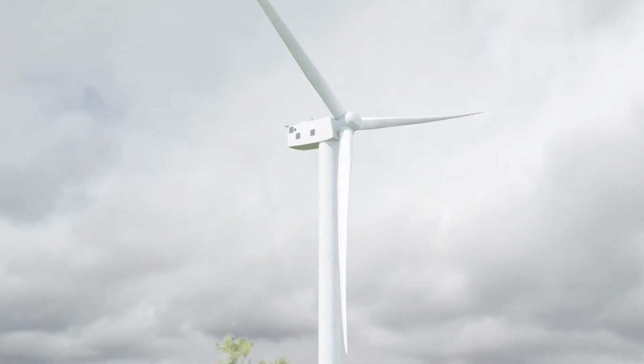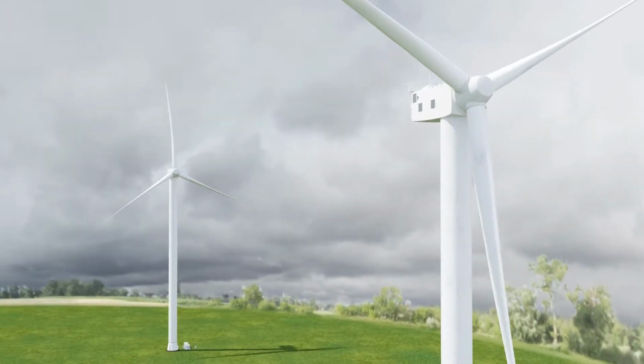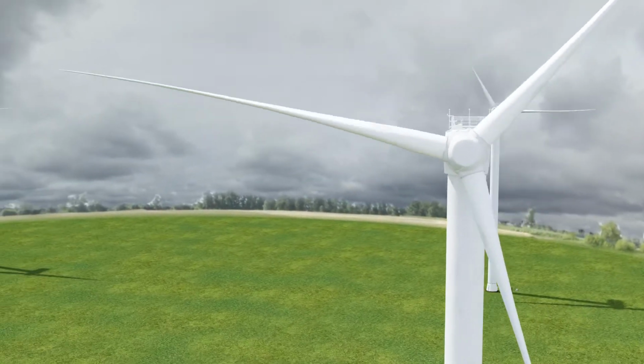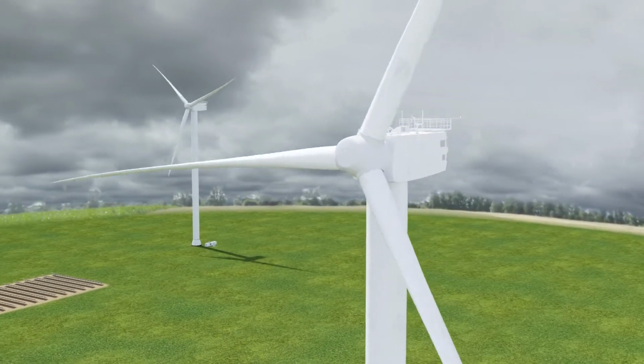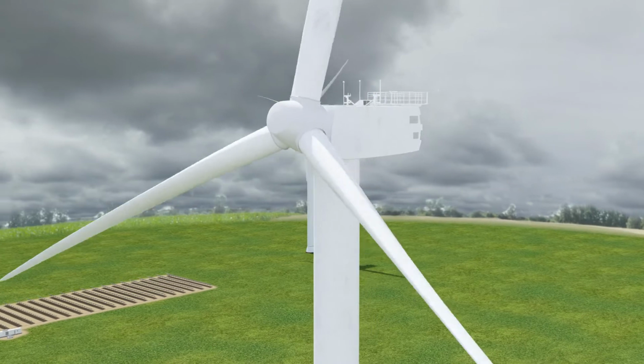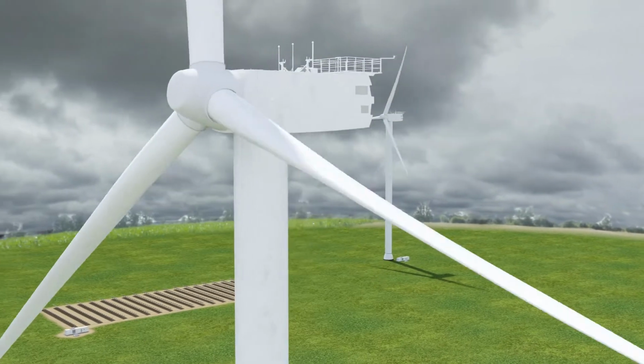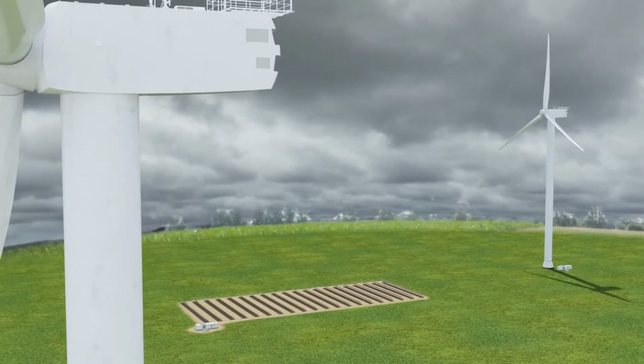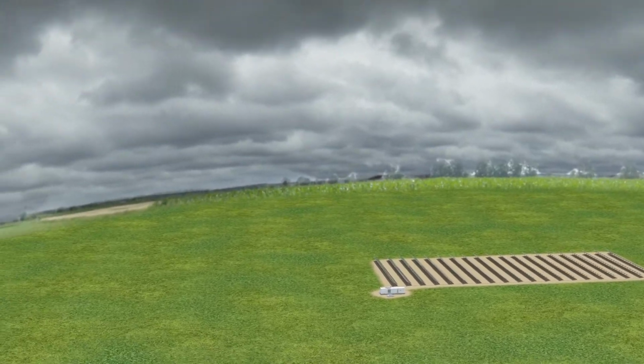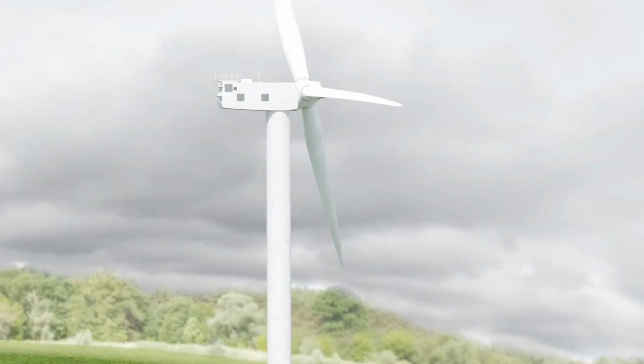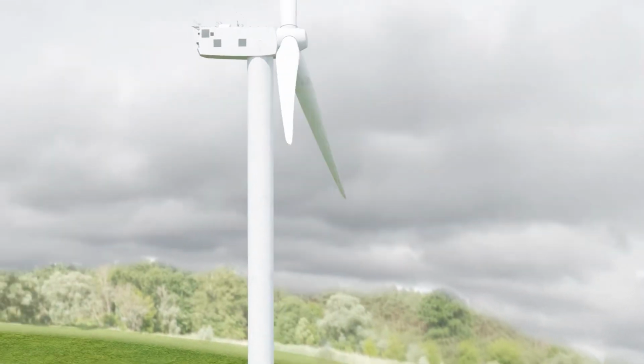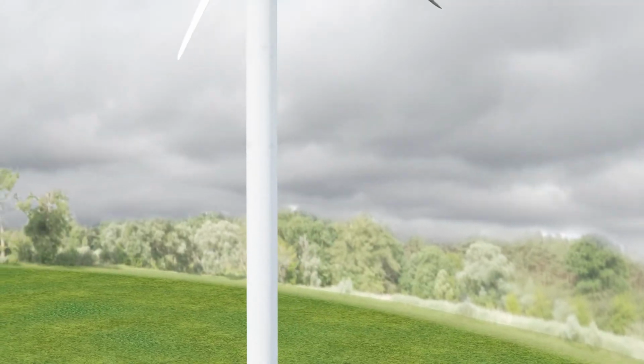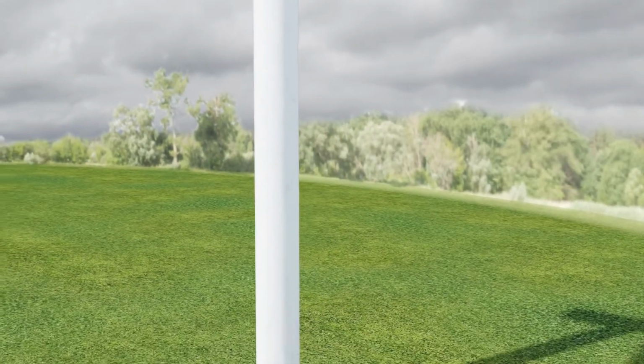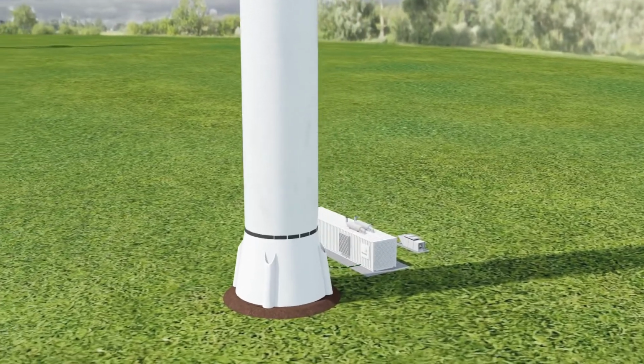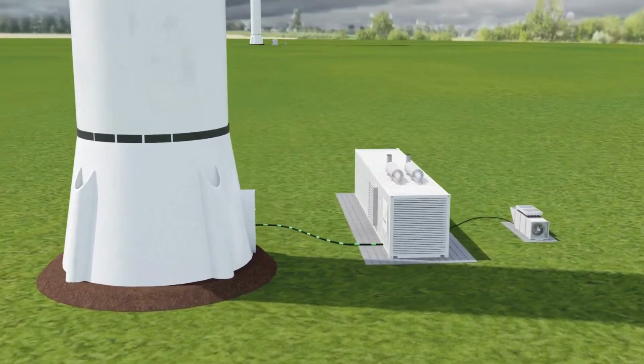Danvest has invented a simple solution. Unlike standard gensets, Danvest-equipped gensets are able to operate lower than the 30% load threshold for longer amounts of time. They even go all the way down to zero load. Danvest will dump energy peaks and will respond fast at all times. By low-loading the engines, a very high amount of wind and/or solar penetration can be achieved.